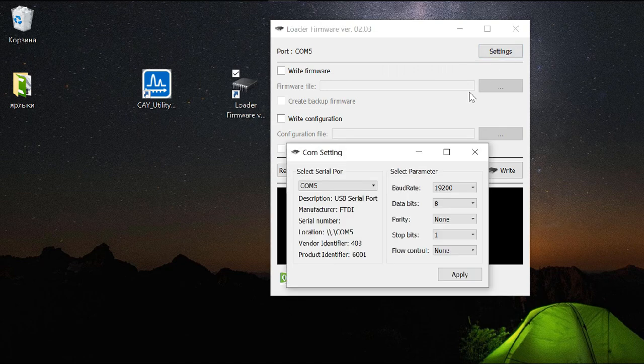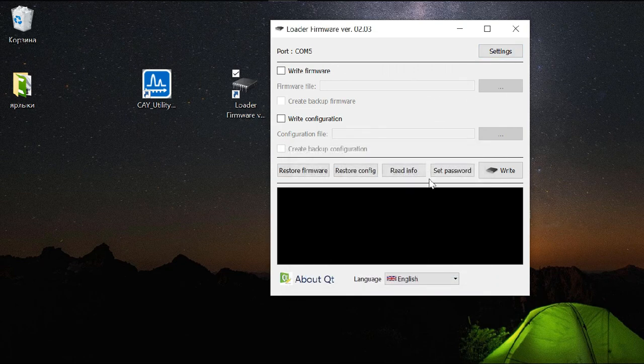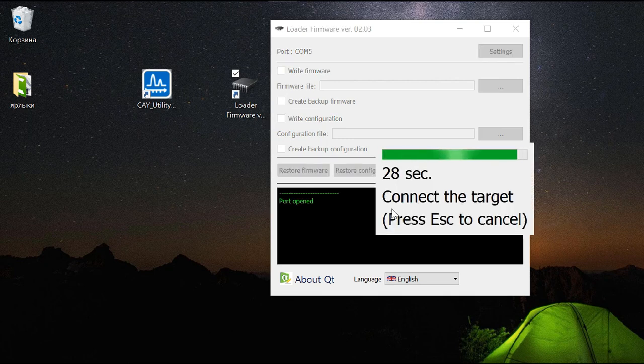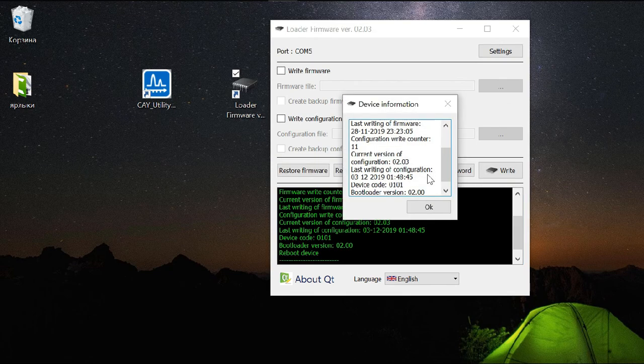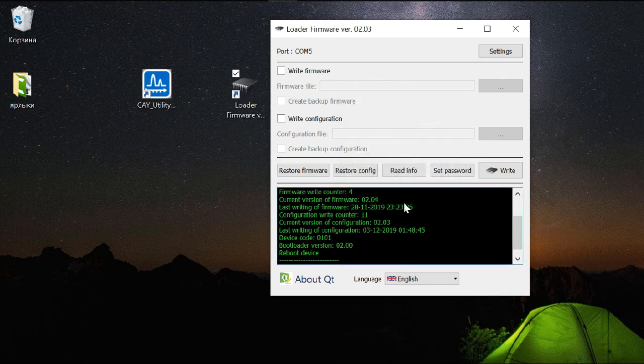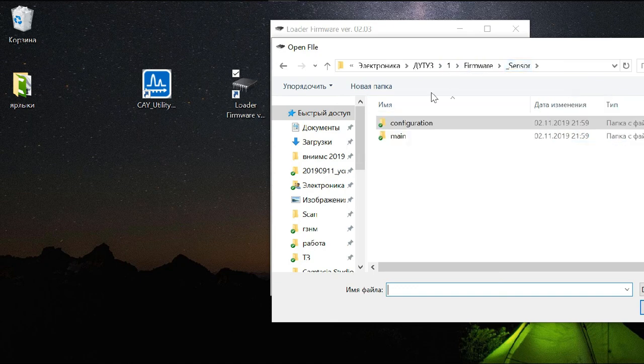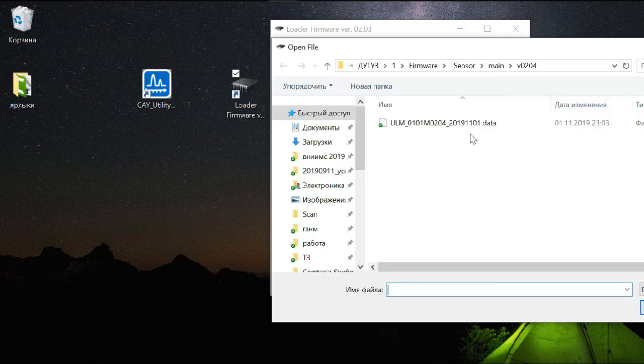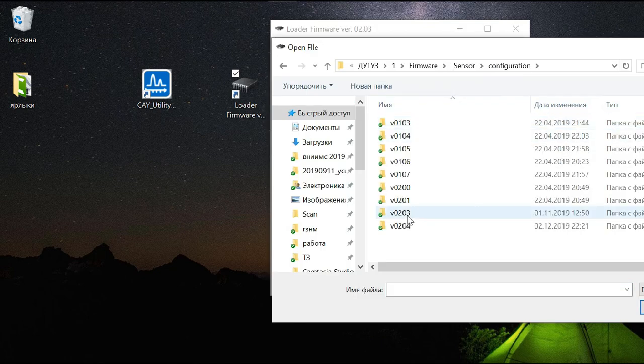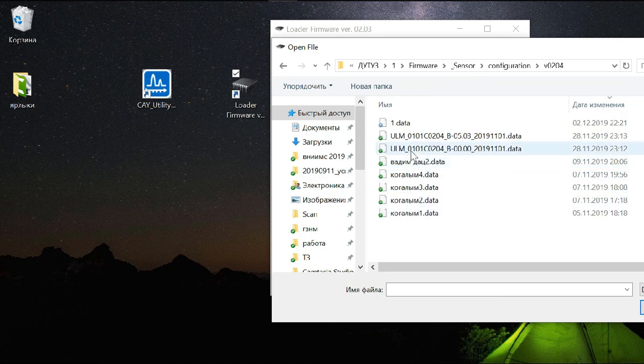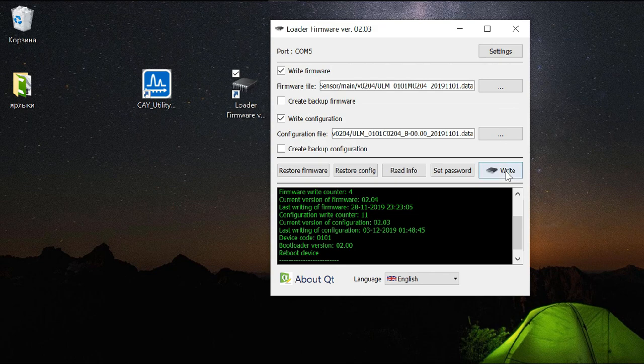Let's update the sensor firmware. Start the firmware loader. Choose the actual COM port. Let's read data from the sensor. Power off the sensor and then power on. We will read the current firmware version and configuration version. Choose the firmware file. Choose the configuration file. Click Write. To start flashing, we have to disconnect the sensor from power shortly. Waiting for firmware flashing. The new firmware will start after power off.